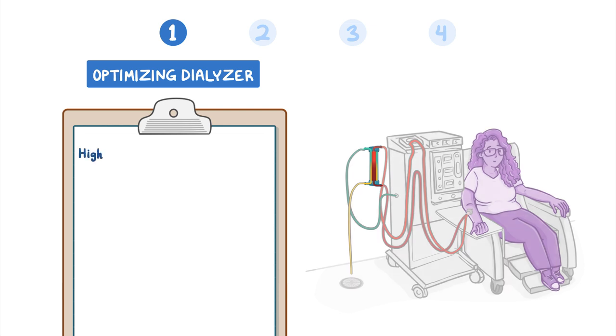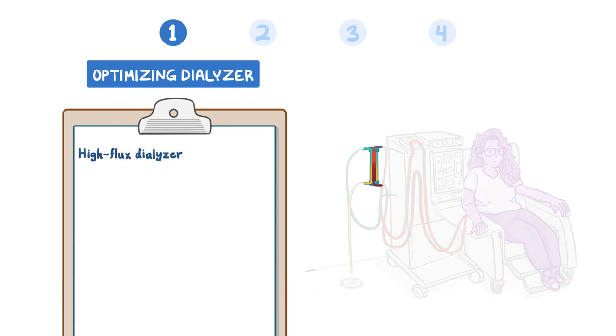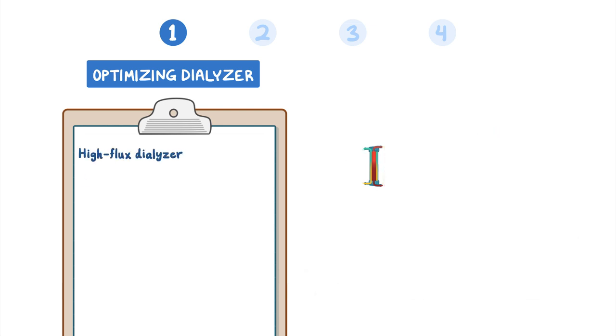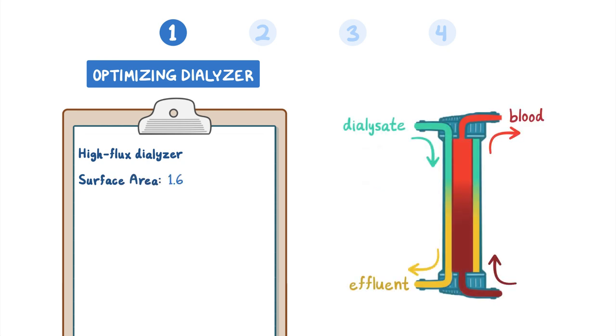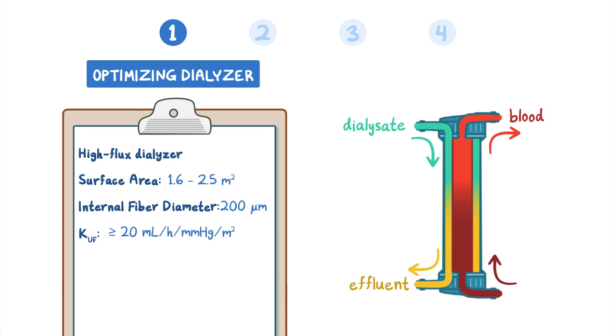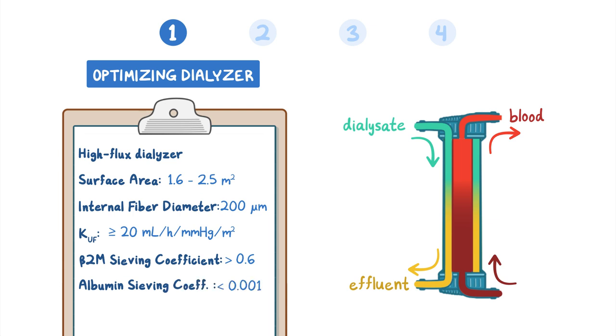Step 1 involves optimizing dialyzer surface area and type. It is important to use a high-flux dialyzer appropriate for hemodiafiltration, typically with a surface area between 1.6 and 2.5 square meters, an internal fiber diameter of at least 200 microns, an ultrafiltration coefficient greater than 20 milliliters per hour per millimeter of mercury per square meter, a beta-2 microglobulin sieving coefficient greater than 0.6, and an albumin sieving coefficient less than 0.001.